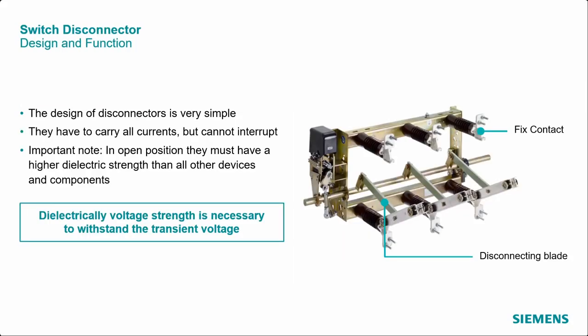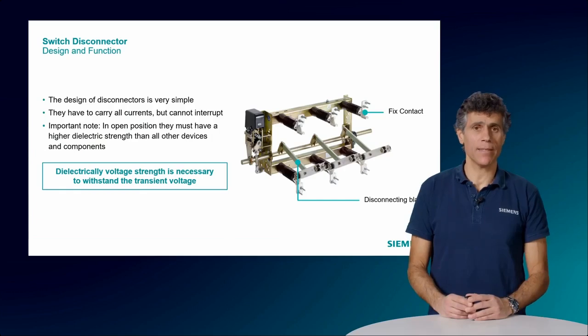And now another device, the switch disconnector. It combines the properties of a disconnector with the ability to switch a circuit under load, meaning under normal operation conditions. Similar to the switch, the disconnector and the contactor, it also cannot break short-circuit currents. The distinguishing characteristic of this device is its capability of withstanding the transient voltage, and that is exactly when it's used instead of a switch, when that capability is needed.